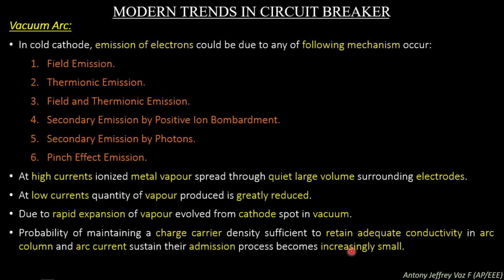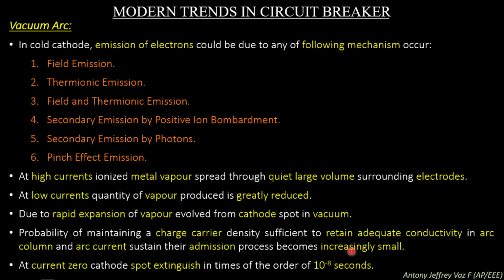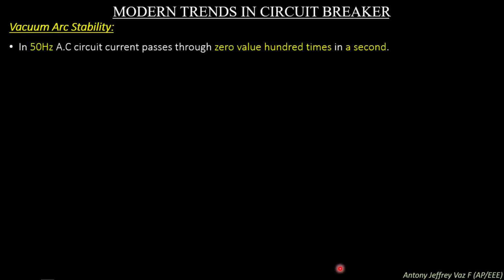So, the conductivity created by the vaporized metal parts should have an increasingly small value of conduction path. So, this admission process of arc current through this vaporized metal should be sufficient to produce the arc in vacuum. At current zero, the cathode spot extinguishes in times of the order of 10 power minus 8 seconds. So, at the current zero position, the spot will extinguish within a fraction of a second, in the order of 10 power minus 8.